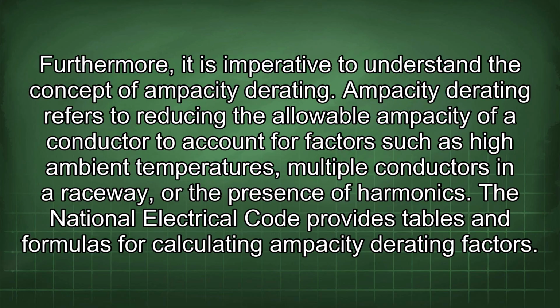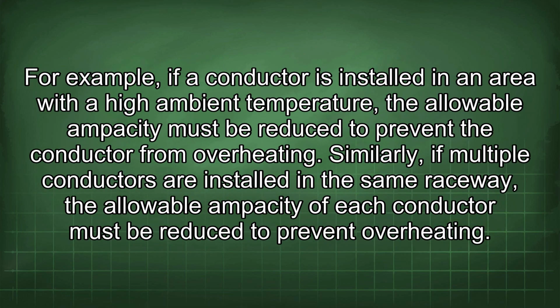Furthermore, it is imperative to understand the concept of ampacity derating. Ampacity derating refers to reducing the allowable ampacity of a conductor to account for factors such as high ambient temperatures, multiple conductors in a raceway, or the presence of harmonics. The National Electrical Code provides tables and formulas for calculating ampacity derating factors. For example, if a conductor is installed in an area with a high ambient temperature, the allowable ampacity must be reduced to prevent the conductor from overheating.